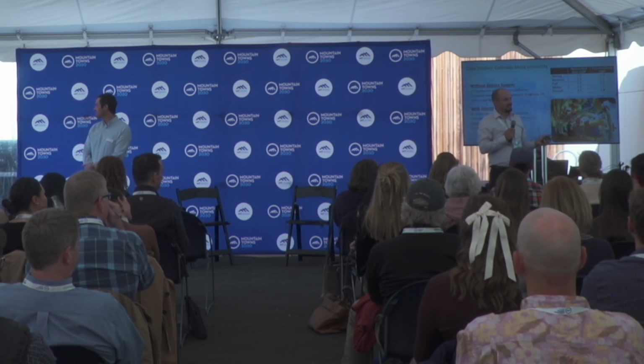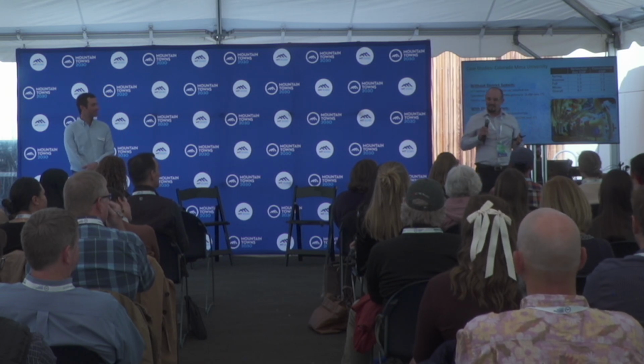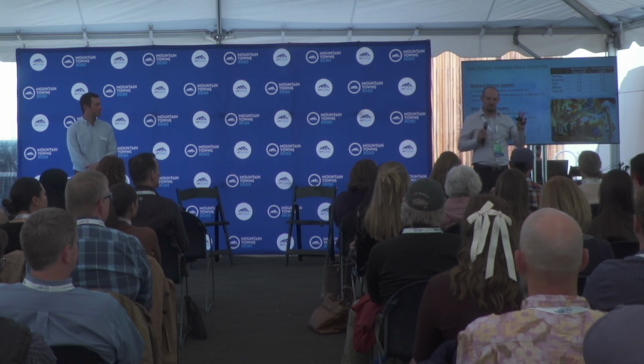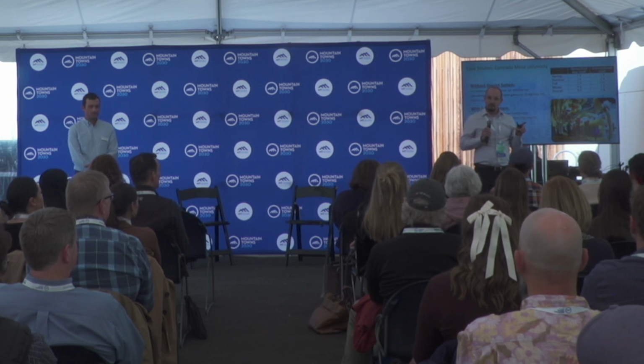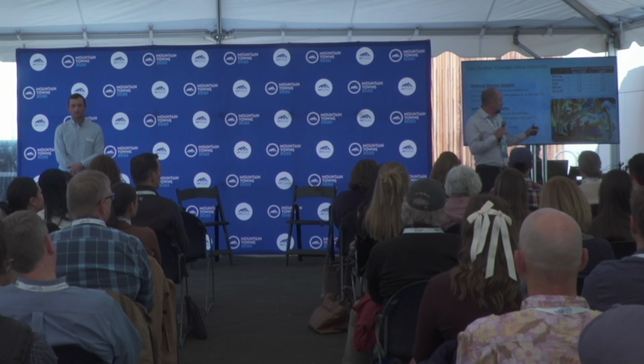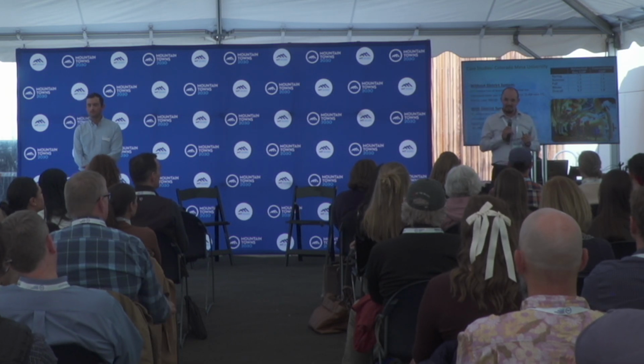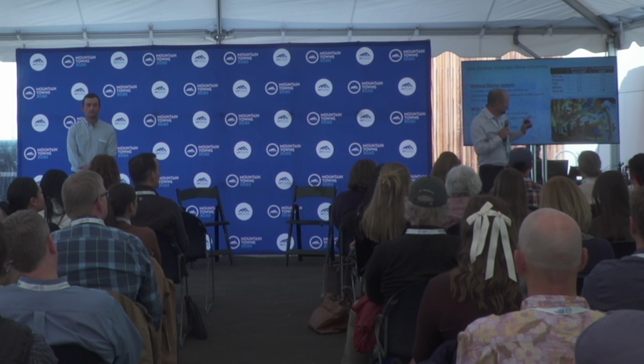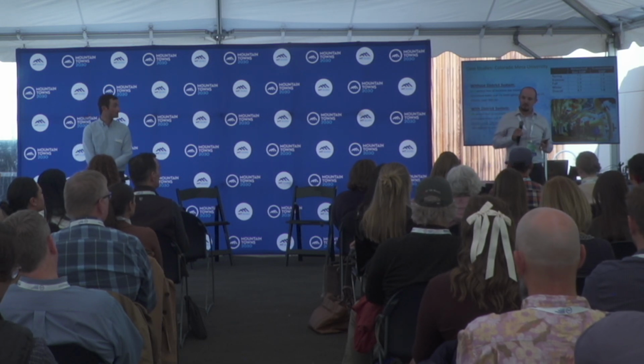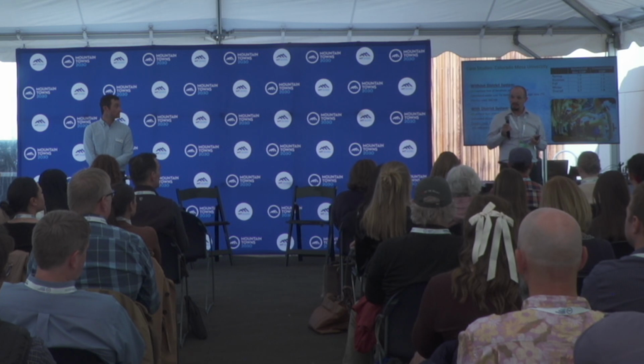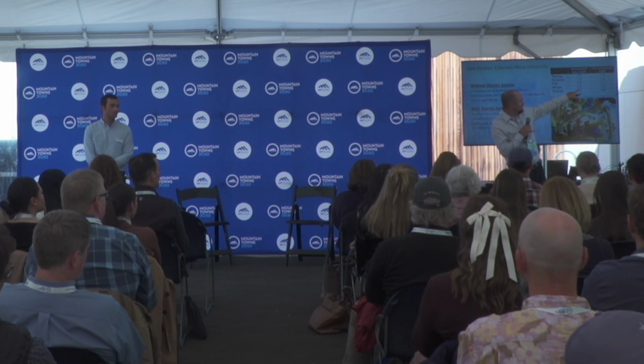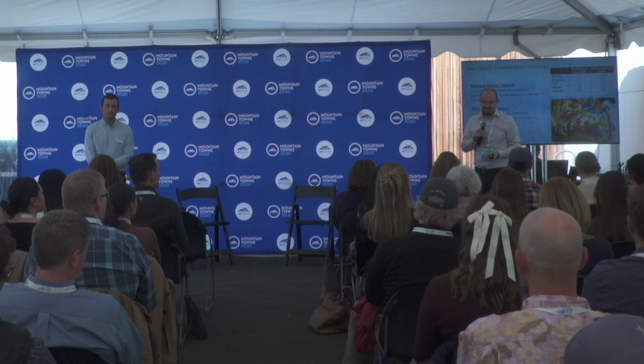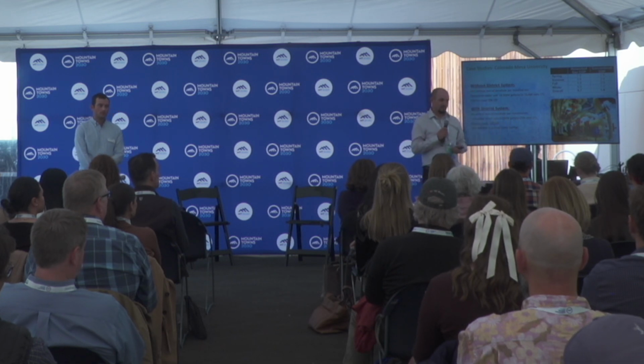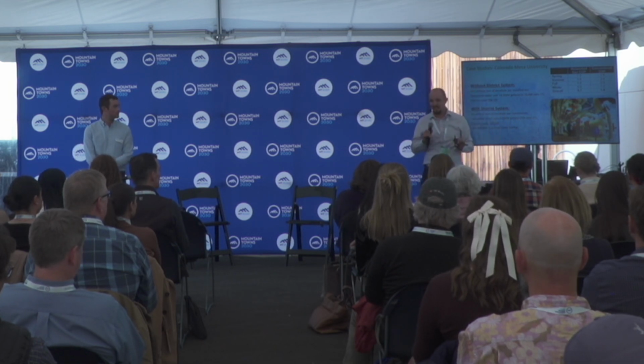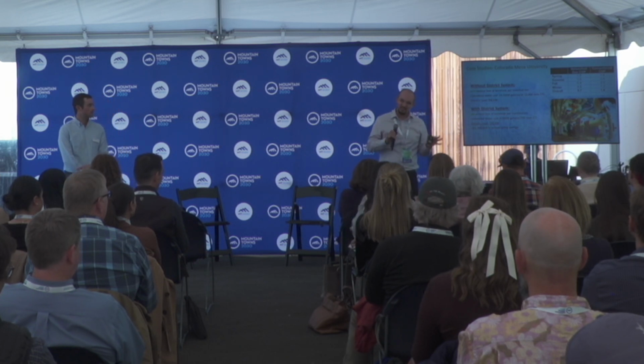What's crazy about this is that in the buildings, the heat pumps themselves that condition your office or whatever, the sticker only says a COP of 4. So as a system, we're seeing a greater than the box efficiency on an annual basis. Another crazy thing that would be specifically valuable to mountain towns is the heating efficiency is 8.9 during the winter. I'm trying to tamp down my enthusiasm, but that's a really good number.